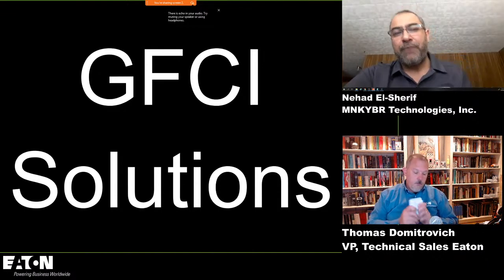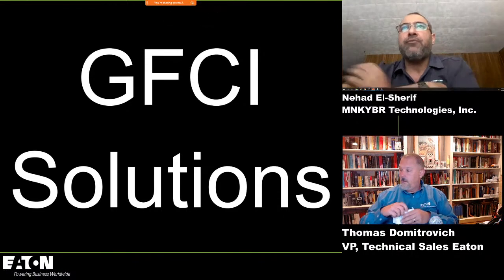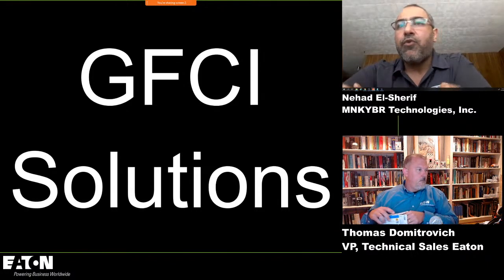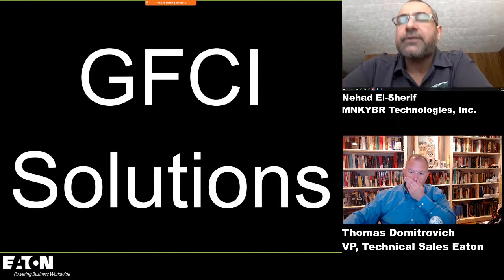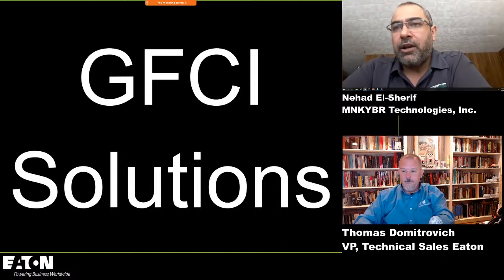But the point I wanted to make is the new UL standard, and it's not quite new anymore. It came into effect in July 2015, and required that GFCIs, and this applies to receptacles and breakers, have a feature called self-test and power denial, which means that the electronics, you think of it as a watchdog in code.